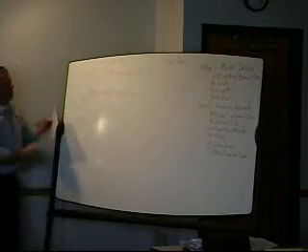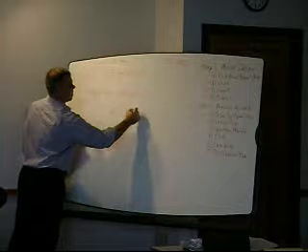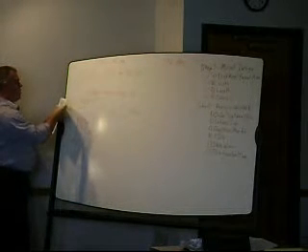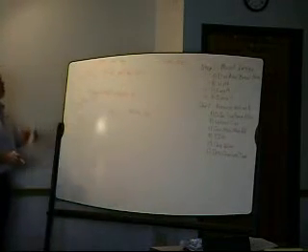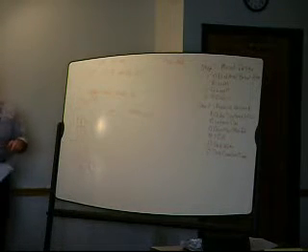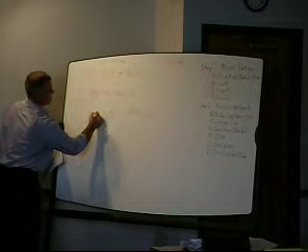Now we need to know what our hole spacing is, right? 50 foot. How do we figure out what I need, 20 holes on a 50-foot run? How do I figure that out? 50 divided by 20, right? And we came up with 2.5 feet. 20 holes along a 50-foot run, 2.5 feet. And that again takes into consideration that I want 6 square feet per orifice, served by each orifice. 6 square feet. Okay?